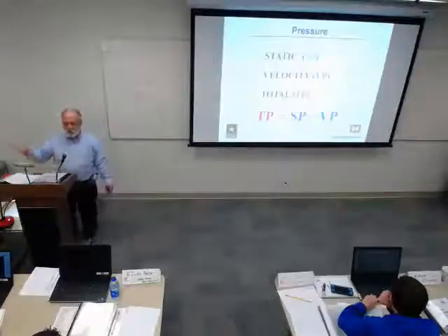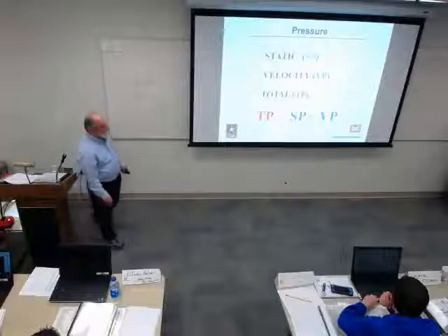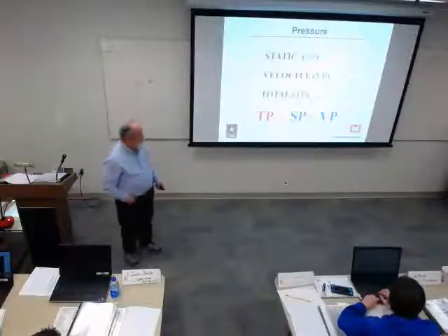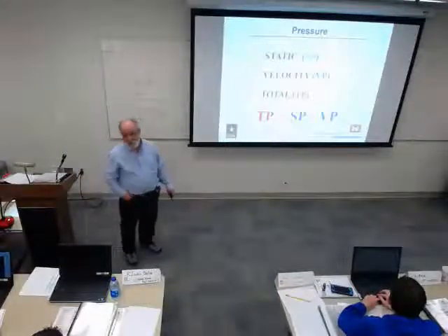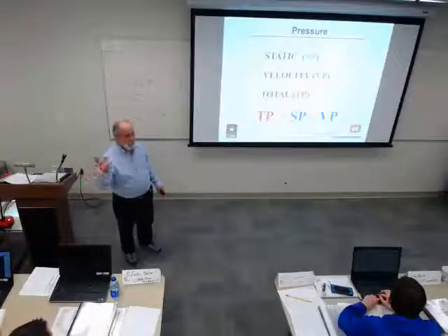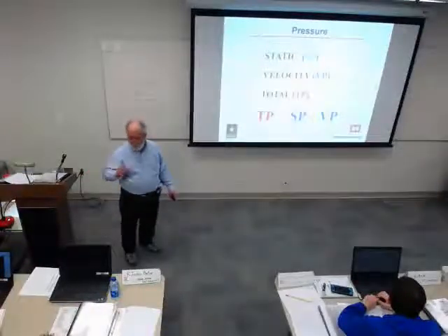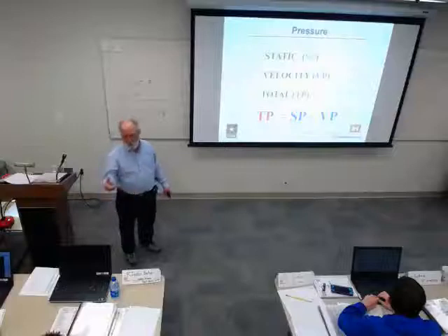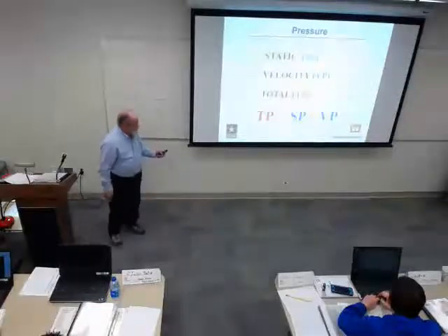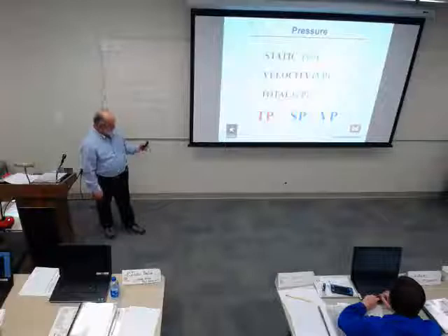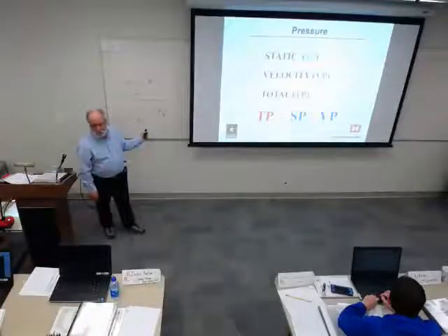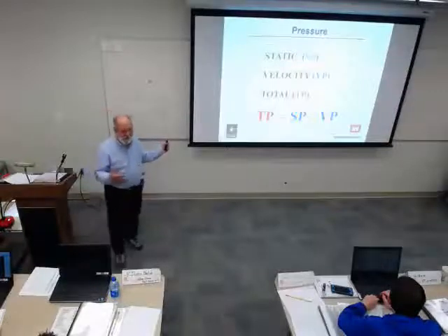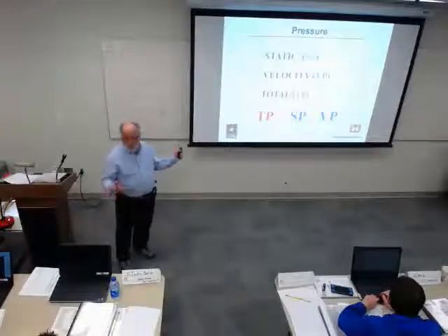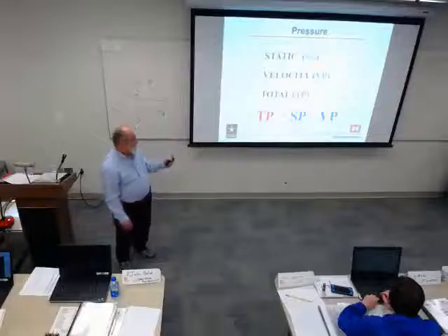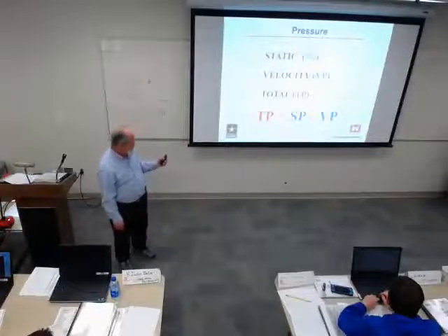For some people, it won't make any difference. But basically the kinetic energy is the velocity pressure, and that's what gets dissipated. And that's why, in the design course, we look at velocity squared and come up with our losses. That's also what generates the noise, the velocity pressures. Noise is energy dissipation also, and that comes from the velocity component.